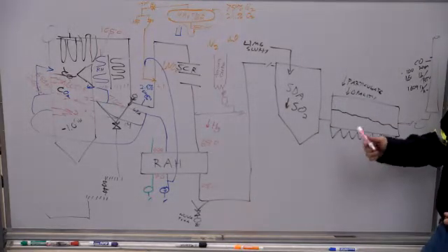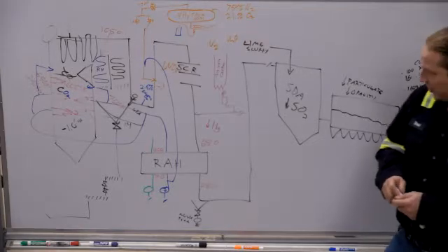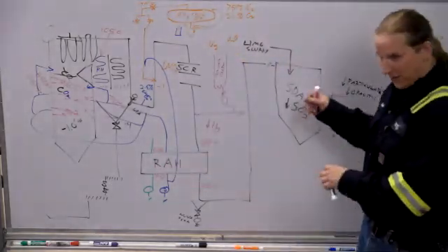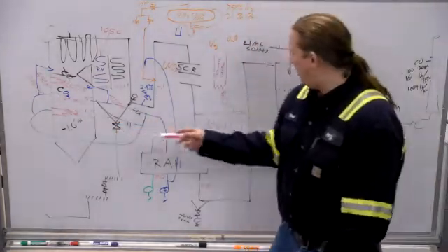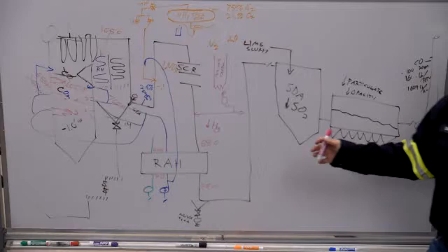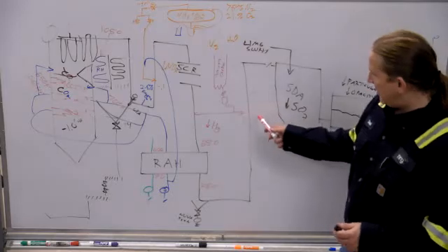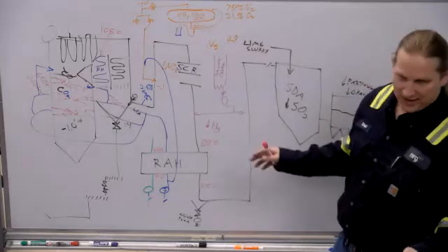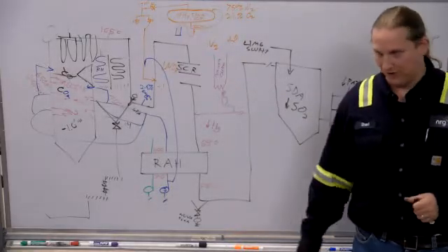And that is because we do something else to also control mercury. Calcium bromide. We add calcium bromide to the coal. Calcium bromide gets sprayed on the coal when it's going up into the silos. And then that makes the carbon way more effective. I don't know the physics. I don't have an explanation for how that happens. But it used to be that to make our limit, we had to have 2 of these things running at 40% most of the time, 20 to 40%. And now we have one of them running at less than 10% most of the time.